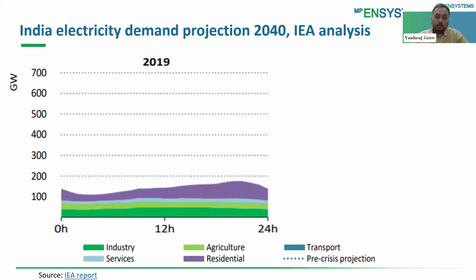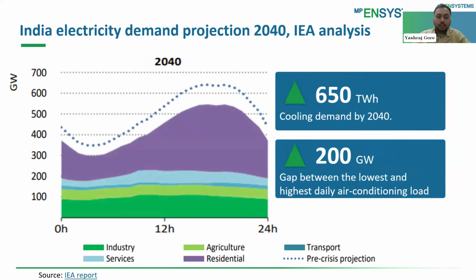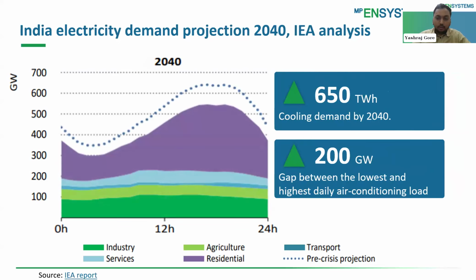So now we came to our topic for this webinar. Here you can see the different demands from the different consumers, and the study shows how your cooling demand will impact the overall load curve, which basically comes from the residential side. So your total load will be 650 terawatt hours in 2040. And you can clearly see the difference of 200 gigawatt between your lowest daily curve and highest daily load.